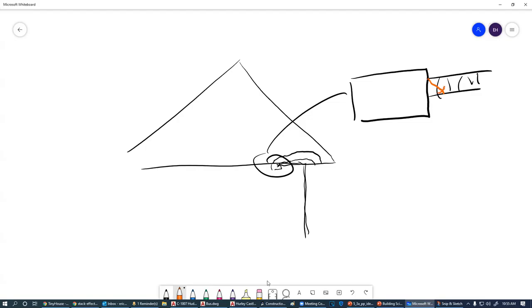This flapper is normally closed, and then when you turn it on, the wind blows it open. Well, because I didn't have any type of louvered vent across this at the time, because I didn't have a soffit on here, a little birdie got in here and decided he's going to build him a nest. So the flapper was stuck open, didn't have good airflow outward, but it was open all the time. I had the presence of cold air coming in and hot air leaving out. So make sure that these flappers work.